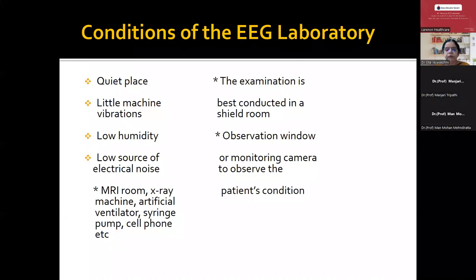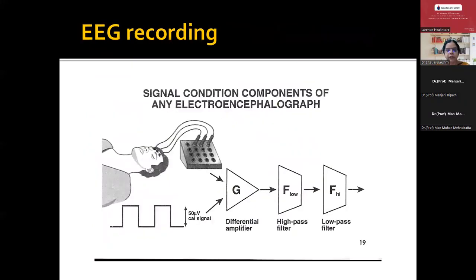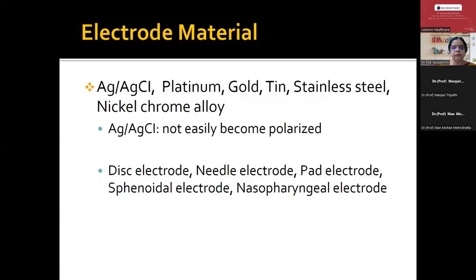The EEG lab should be away from large AC units in the hospital. It should not be close to any MRI or X-ray machine, and examination is best conducted in a shielded room if possible. There should be an observation window for the technologist. To summarize the EEG system: it goes to the junction box, and after that the machine amplifier contains a differential amplifier, after which the EEG signal goes through a low frequency filter and a high frequency filter.